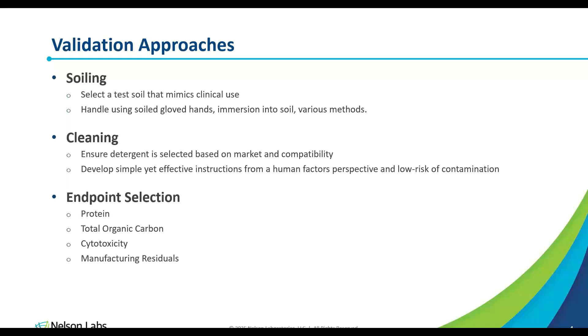Now, when we get into 3D printed device validations, I know the term gray area is like, oh my goodness, but it really is a true issue. With these two documents, ST98 and the FDA guidance document, they seem to be more geared towards reusable devices, even though they still apply to single-use devices that require cleaning at the facility prior to use.